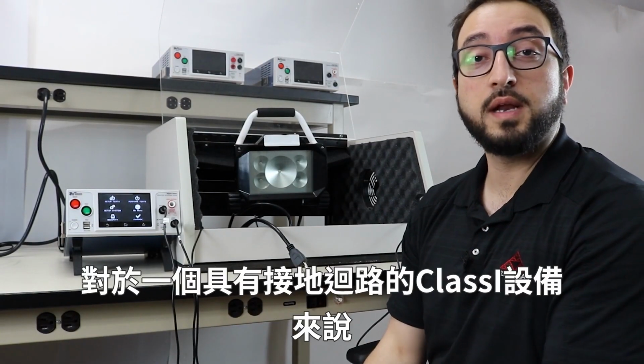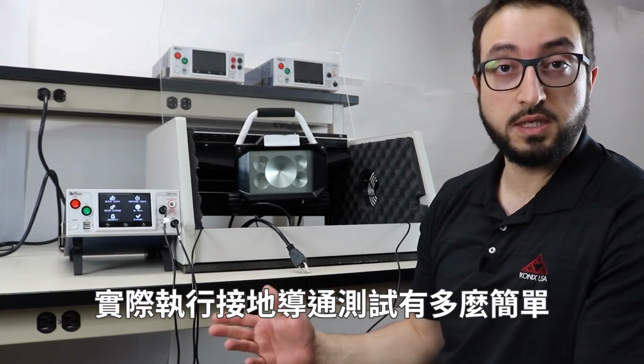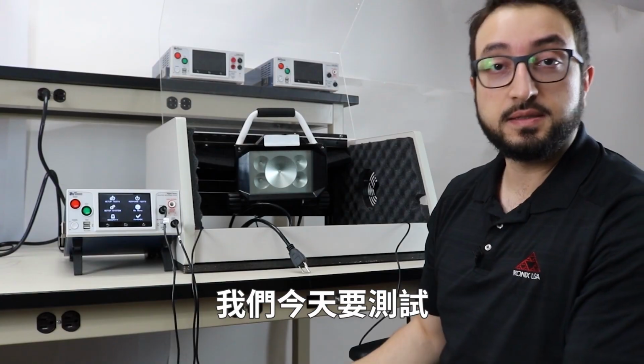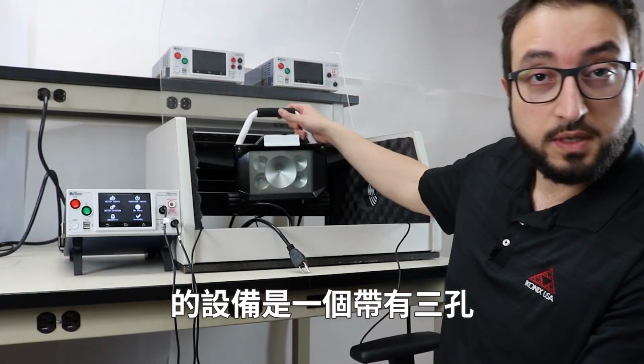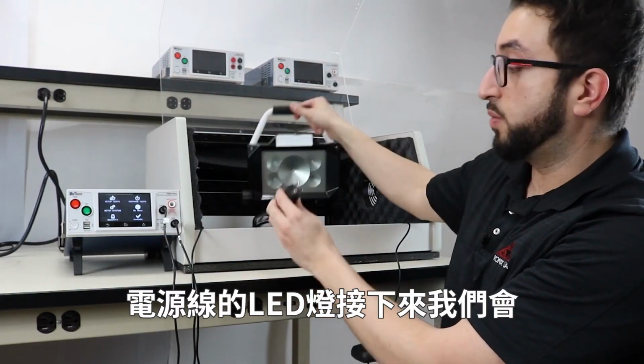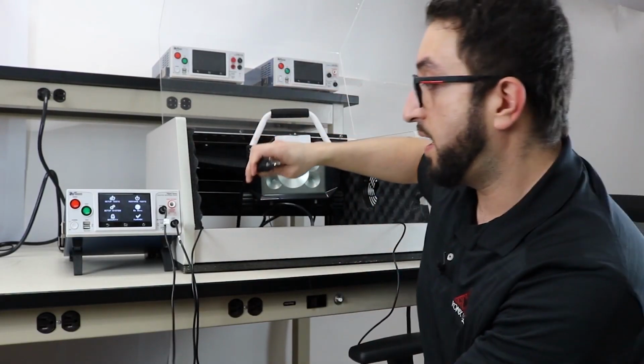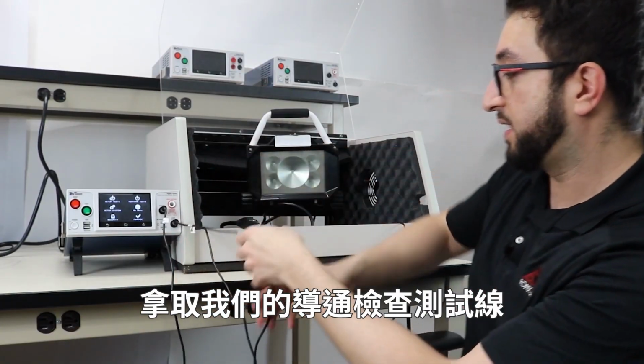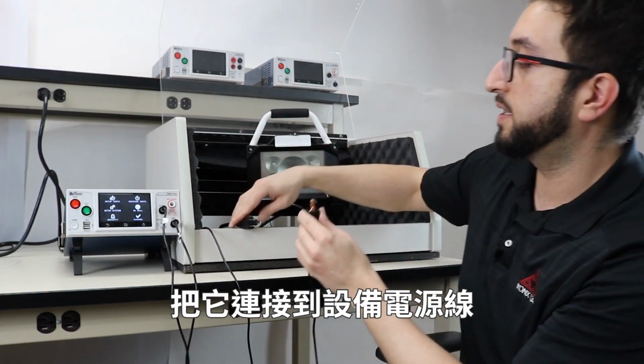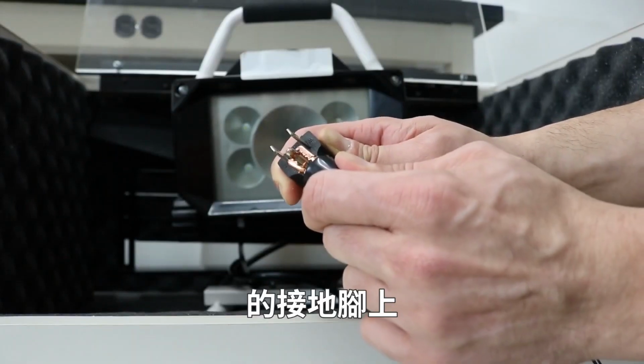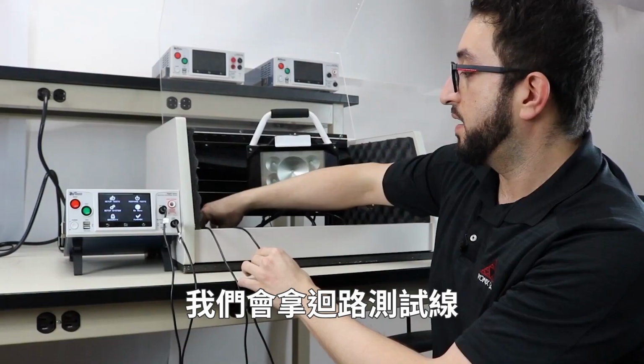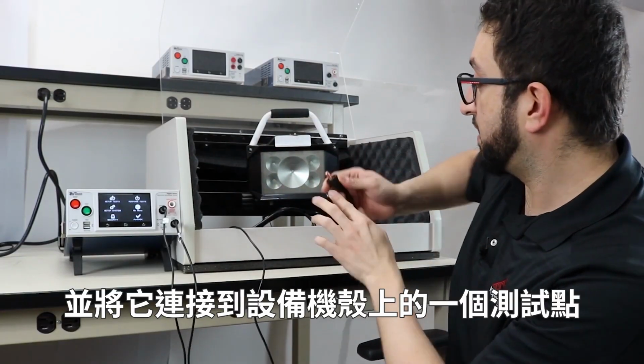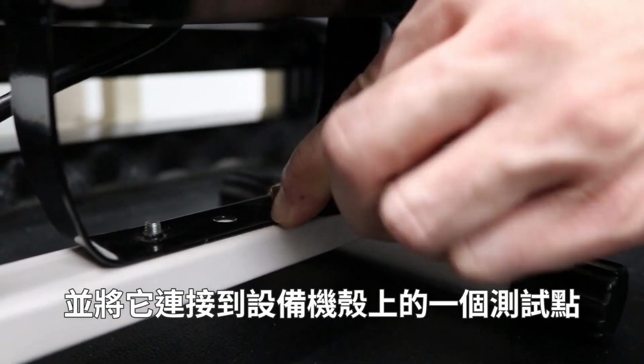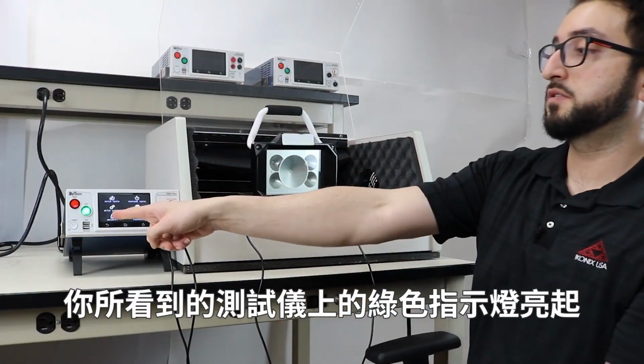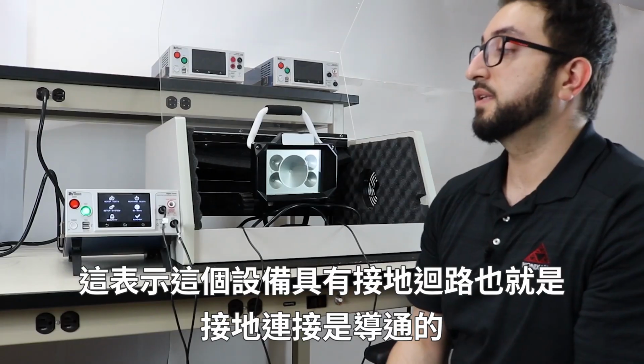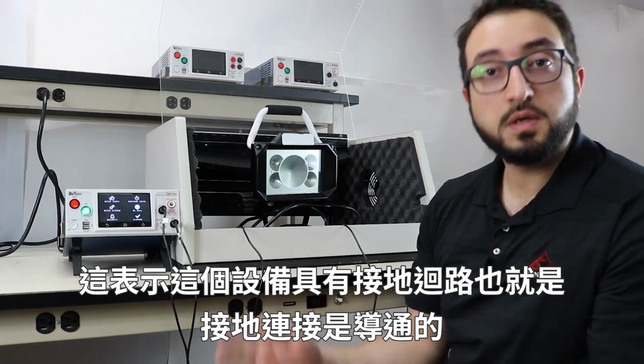Okay, so now let's take a look at how simple it is to actually perform a ground continuity test on a Class 1 device that has a ground circuit. The device that we're going to test today is an LED lamp with a 3-prong line cord, and we're going to take our continuity check lead, which is right here. We're going to connect it to the ground pin on the line cord of the device, and then we're going to take our return test lead and connect it on a chassis point on the device under test. And as you can see on the tester, the green light turns on, which is indicating that this device has a continuous ground circuit.